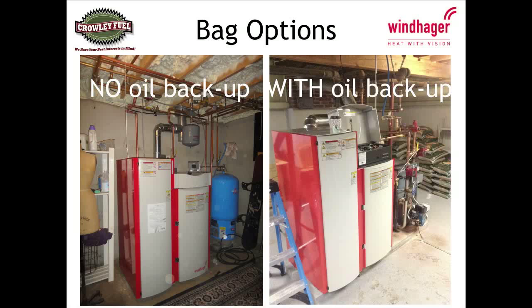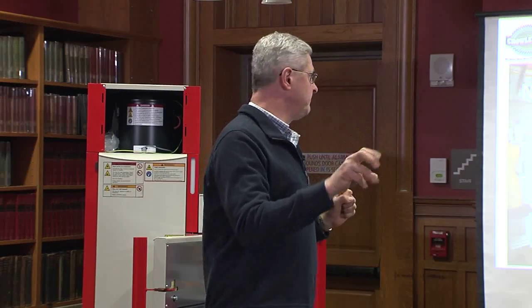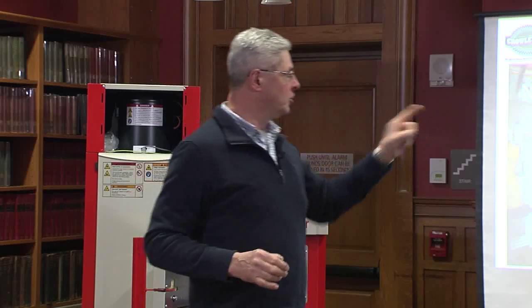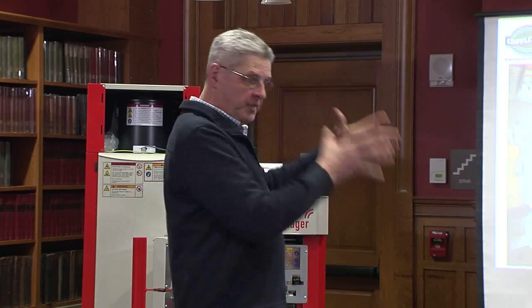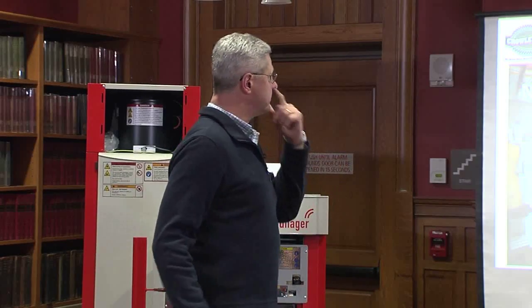So that was a question. Can I keep my oil? And you can. The thing is, what you need is a flue that is lined for a pellet unit. These do not direct vent. If you only have one flue available, you could direct vent your oil burner and put this one in the lined flue. So those are your options as far as oil backup.